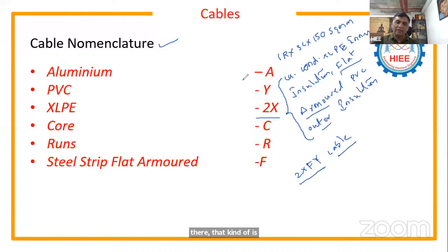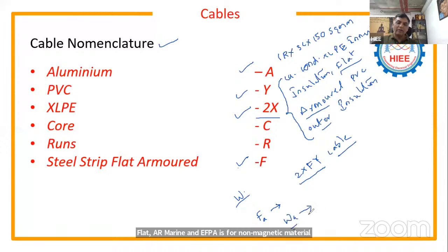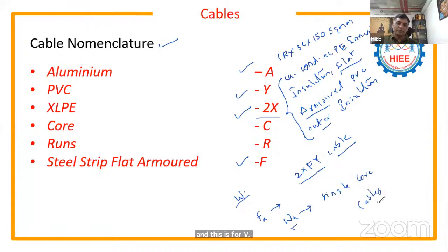Okay, most frequently we use A, Y, 2X and flat armoring and wire armoring. And FA is for non-magnetic material, and this is for wire armoring with a non-magnetic material. This is used for single core cables. This is how we define the nomenclature of cable. Guys, is it clear? Any doubts?